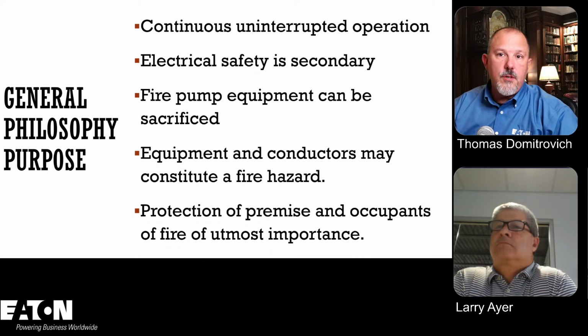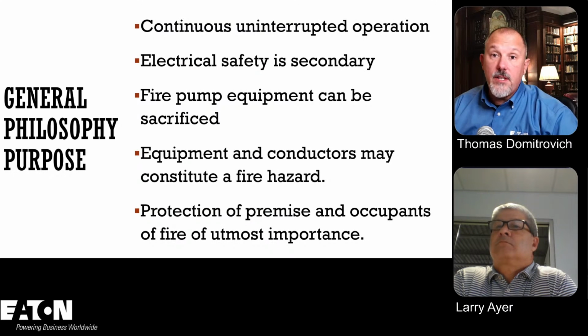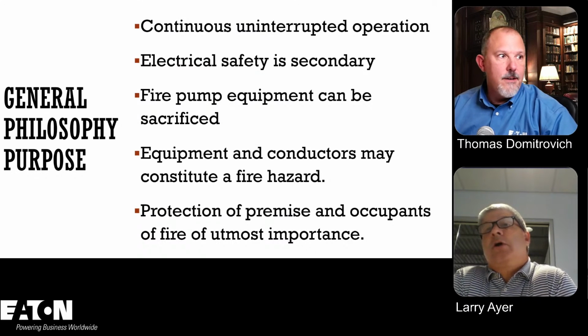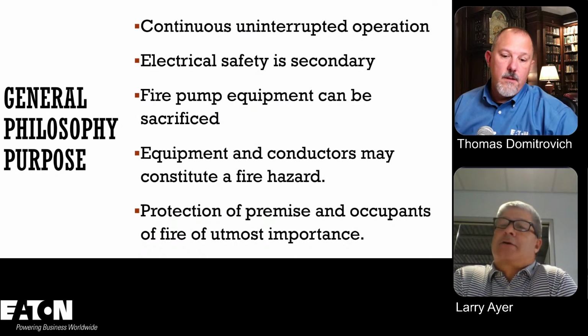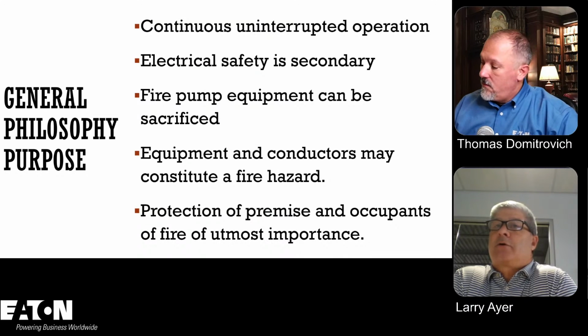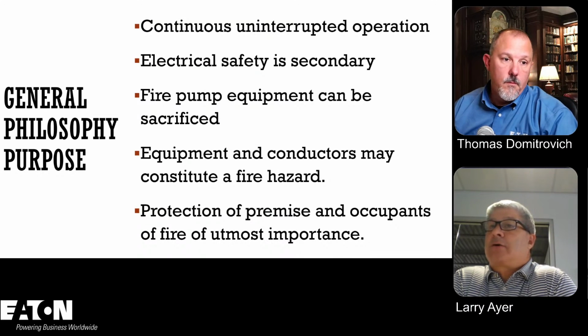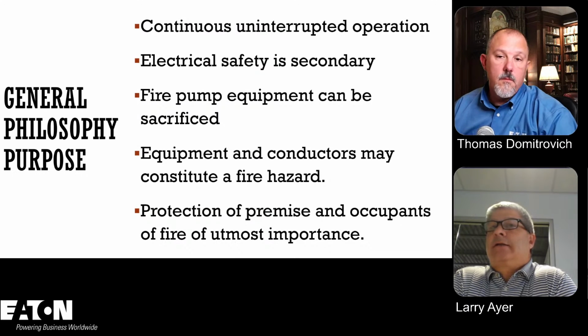But when it comes to, like you said, if there's a locked rotor, or if there is something going on in that motor, I want that puppy to just keep going until I could burn up the wires. I could do other dangerous things, but for the electrical safety aspect, we're not making steps for the electrical workers and things like that, right? We're not putting ground fault in there. That's correct. So we want to make sure that the breaker's sized high enough for the locked rotor. We want to make sure that we have wires that are protected for 2 hours. So we want to do whatever we can to give that fire pump enough time to push that water out to put the fire out.